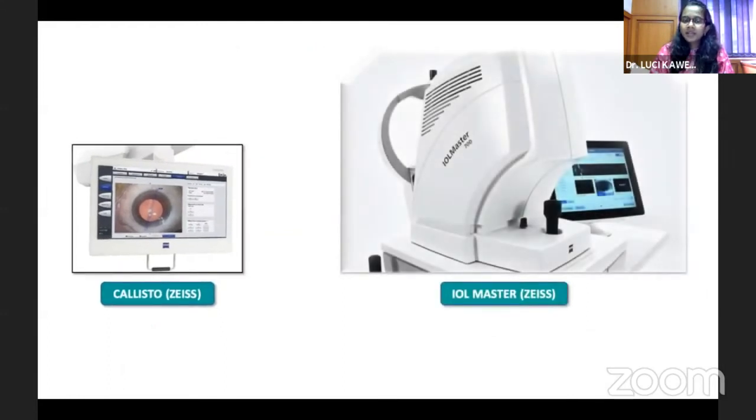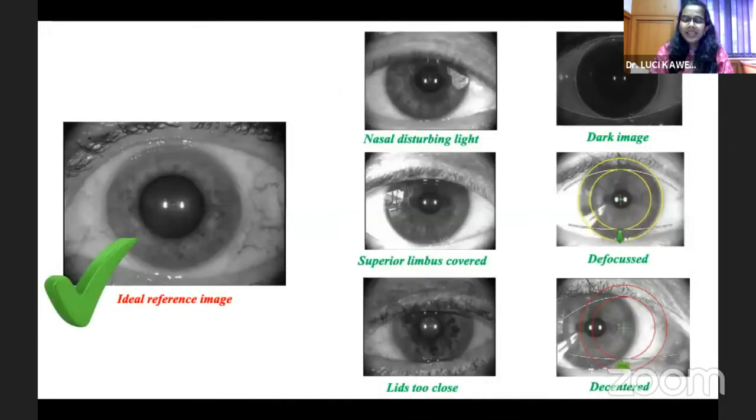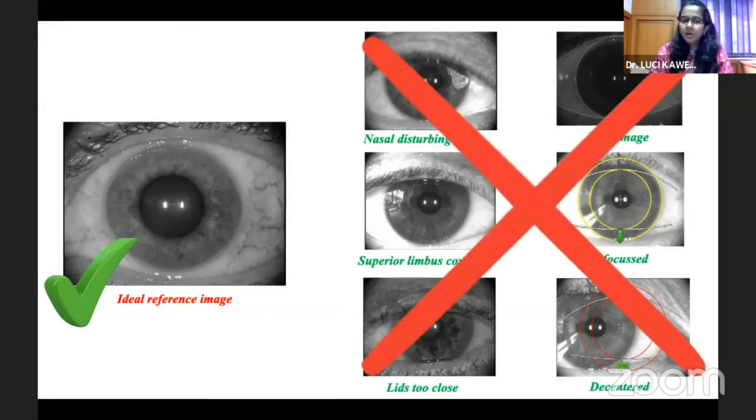At our center we have the Callisto marking system, so I'll go into a little more detail about that. It can be paired with the IOL Master 700 and there's a Callisto Refractive Suite available with a Zeiss Forum EQ Workplace. Once the image is captured on the IOL Master 700, we need to make sure we get a good reference image — one where both the superior and inferior limbus are well exposed, the details of the iris and blood vessels are clearly seen, and the image is well centered. Images with lid obstruction, defocus, or decentration should not be used, as they also affect keratometry quality.